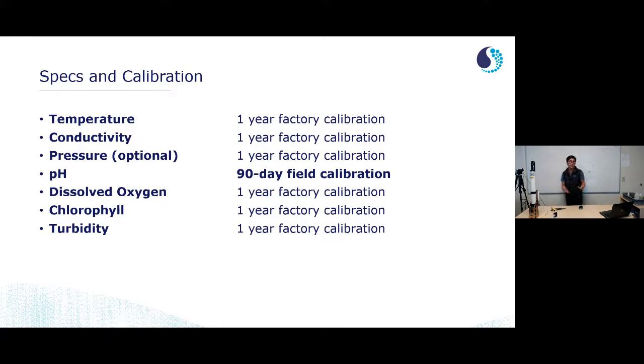That being said, your pH sensor is really the limiting factor of your sensor calibration, with that 90-day, approximately 3 months, versus the 1-year factory calibration of everything else. That being said, in my experience, a lot of these glass electrode pH sensors typically need to be recalibrated every week or every 2 weeks to maintain their spec. We've done a lot of work and research into making sure that this particular sensor can be used in the field for 90 days and retain that 0.1 pH accuracy.